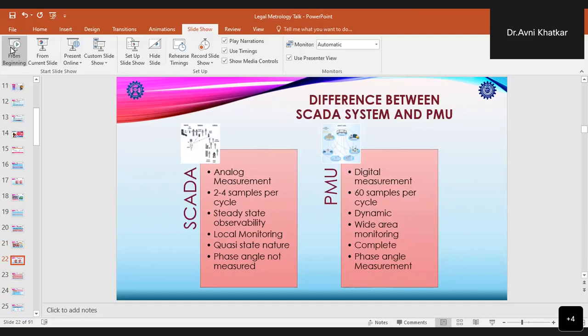SCADA systems, and now we are moving towards having phasor measurement units in the system. So the SCADA systems, which were used till now, are built upon 104 RTUs, and they are used till now in the present grid. So this present grid is primarily managed by using technologies like SCADA, that is supervisory control and data acquisition. And this SCADA system has a refresh rate of 2 to 4 samples per cycle. And hence, it provides only a quasi-static grid visibility.